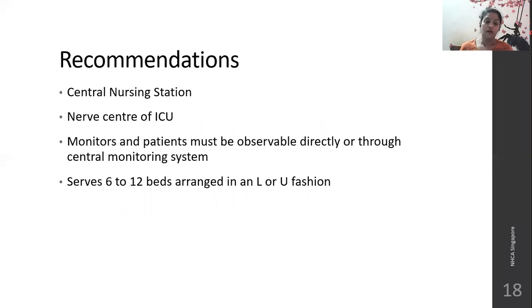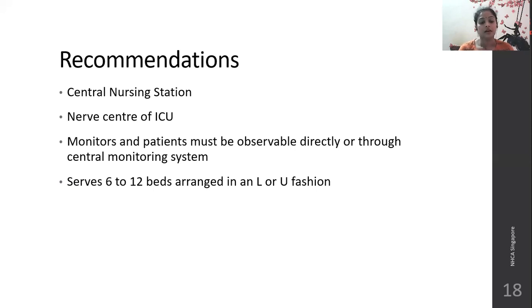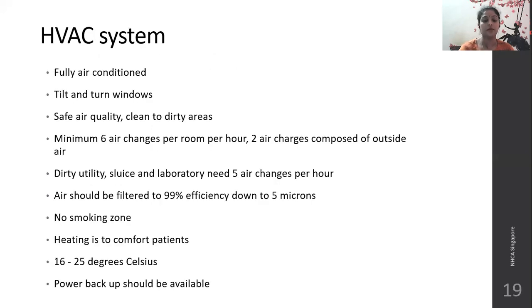The central nursing station is the nerve center of the ICU. It should be equidistant to all patient beds and all patients should be observable from the nursing station either directly or through a central monitoring system. It can be arranged in an L or U shape and serves up to 6 to 12 beds. The ICU should be fully air-conditioned, with minimum 6 air changes per room per hour. Two air changes can be composed of outside air.